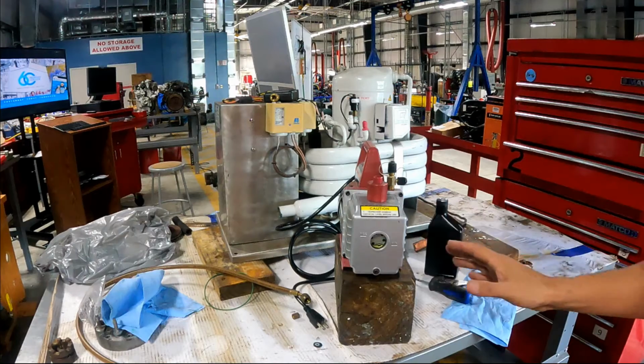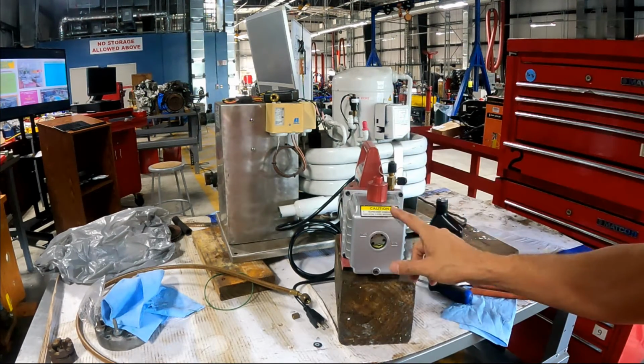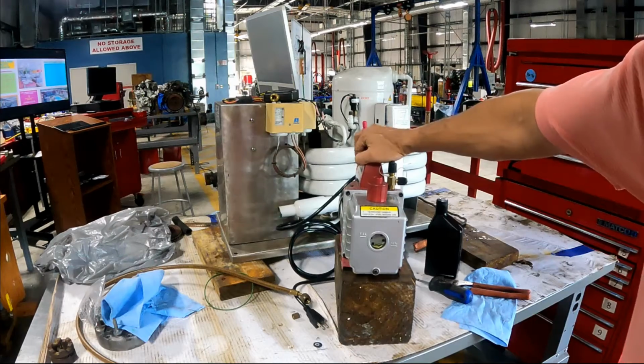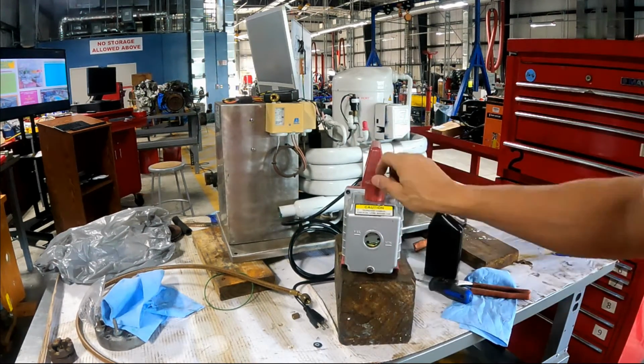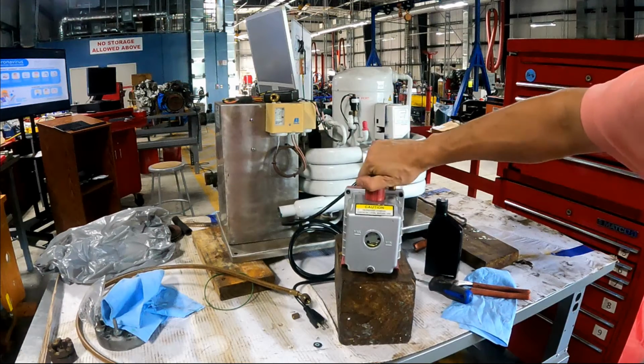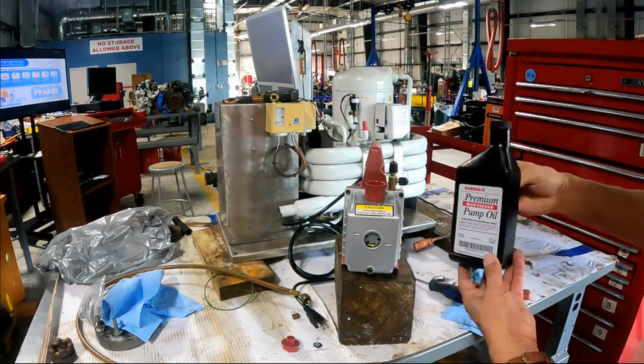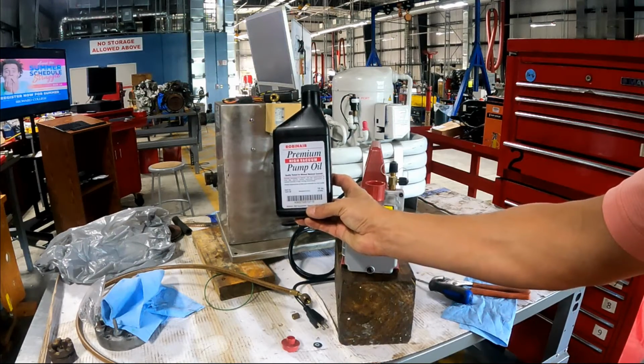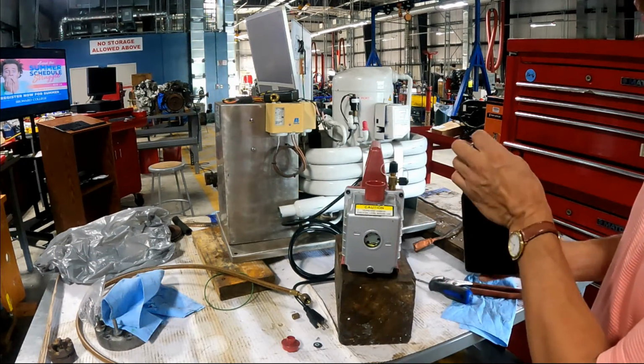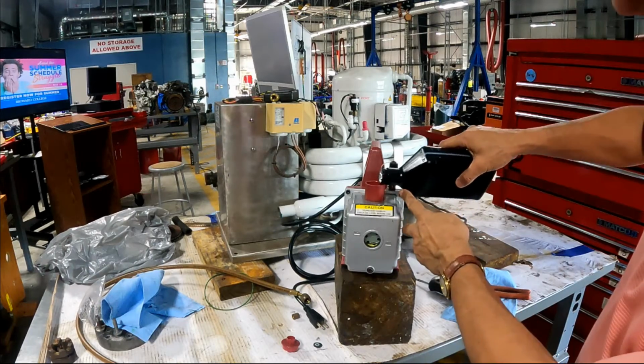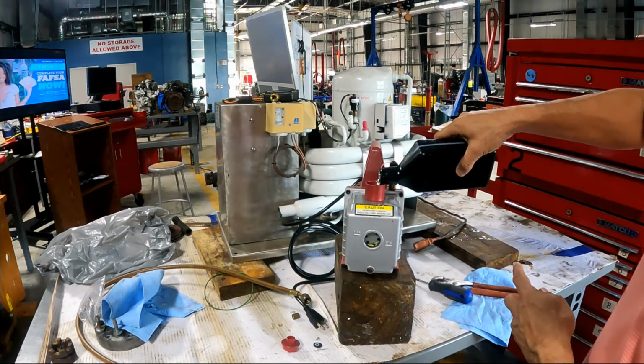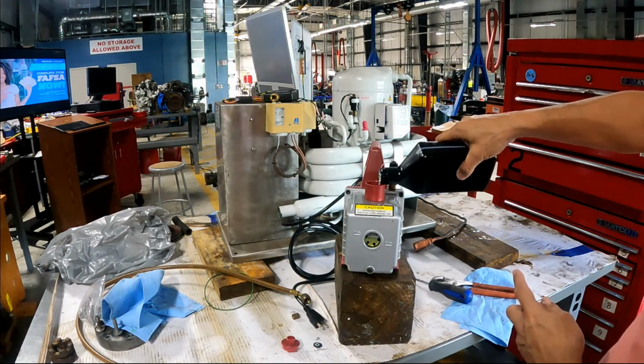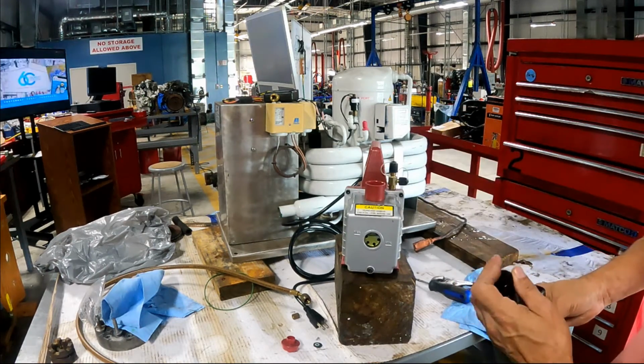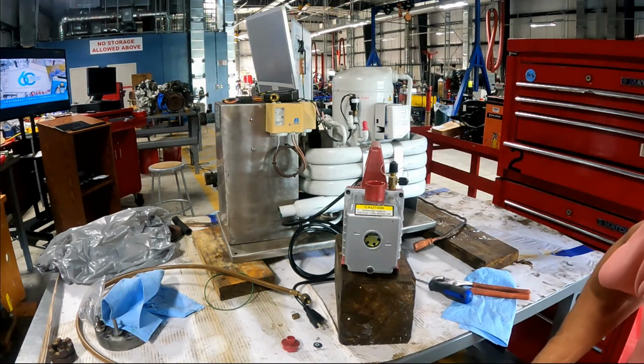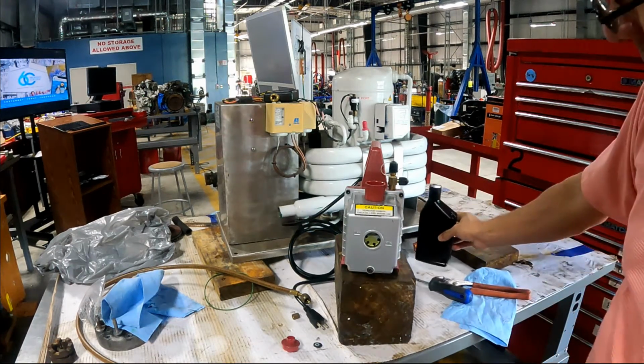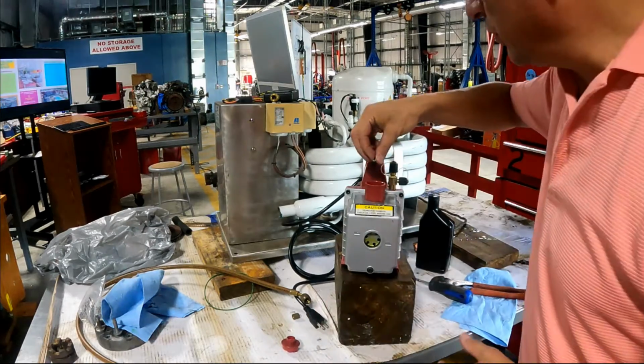We are in front of a chiller unit, and we are going to do the vacuum procedure. First of all, we are going to check the pump. At this moment, the level of the oil in the pump is too low. We are going to add oil into the pump. We are going to add the recommended oil for vacuum pumps, and we are going to check that the oil is at the level. Correct. That's the maximum. We are exactly at the limit recommended by the manufacturer. We are going to put the cap back.